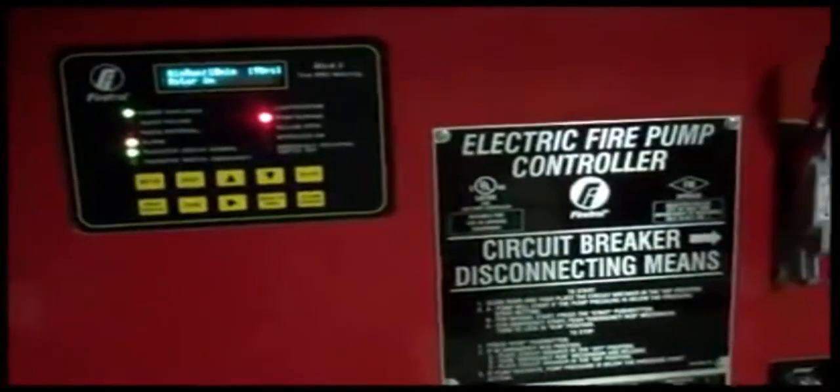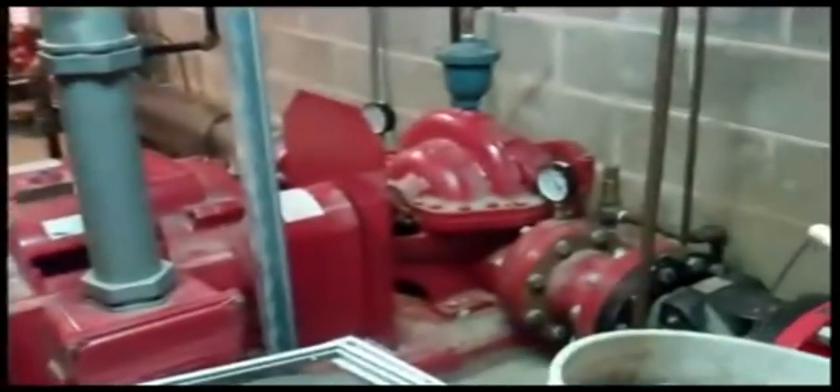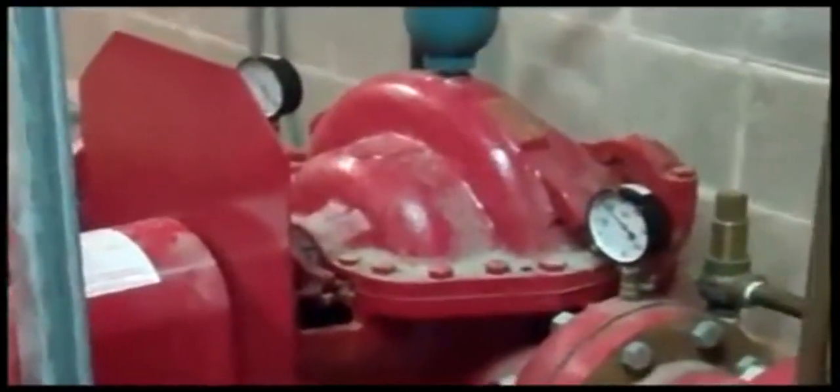With an automatic controller, the controllers will shut down the fire pump after a specified amount of time. For an electric pump, this is 10 minutes.